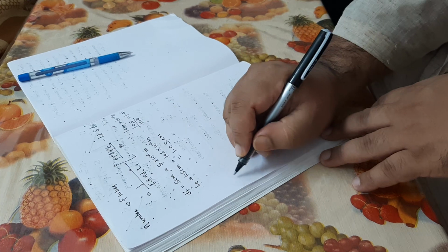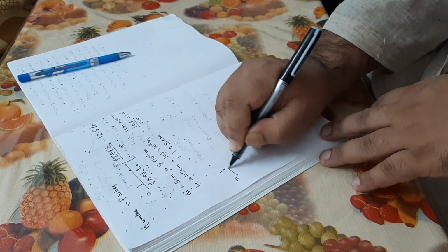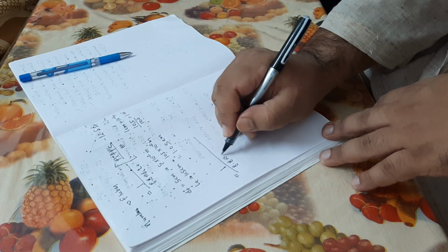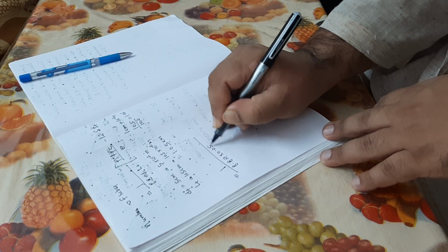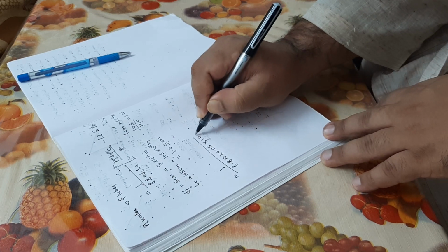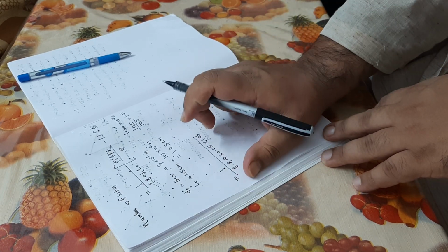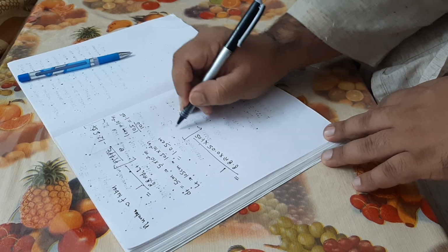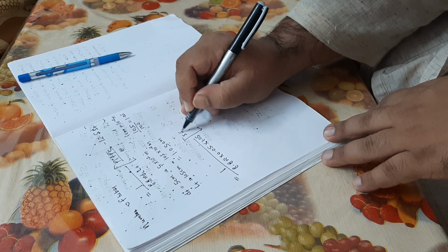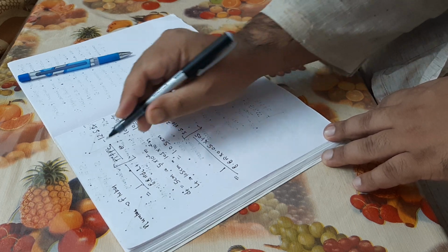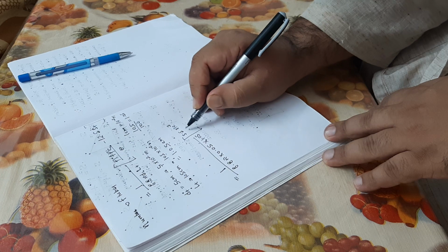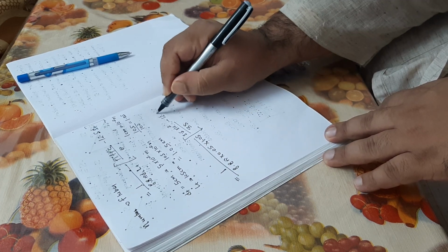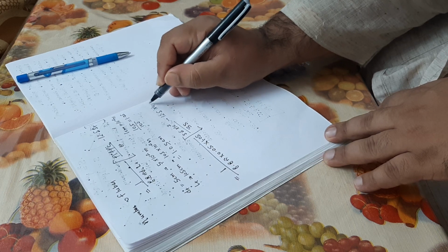Again we have all the values, so we can calculate the number of tubes. So this is 1 divided by 8.8 pi. Instead of dt we are going to write 0.05. Instead of LT we are going to write 1.05, because we have to keep the units into consideration. This is in meter square, and here also we have 5.5 in 10 power 3, because this is in kilowatts, so hence in watts we have to write, divided by 35 minus 12.5 and into 4.92.